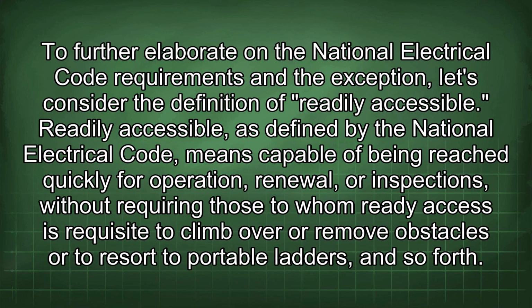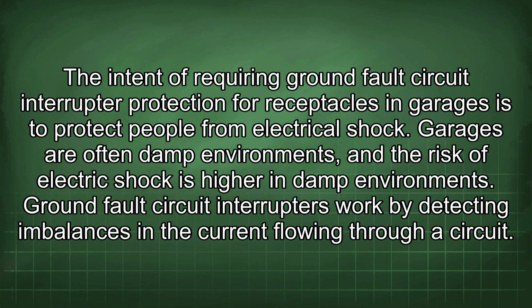To further elaborate on the National Electrical Code requirements and the exception, let's consider the definition of readily accessible. Readily accessible, as defined by the National Electrical Code, means capable of being reached quickly for operation, renewal, or inspections, without requiring those to whom ready access is requisite to climb over or remove obstacles or to resort to portable ladders, and so forth.